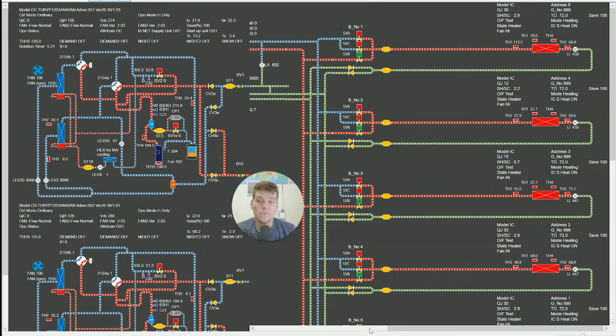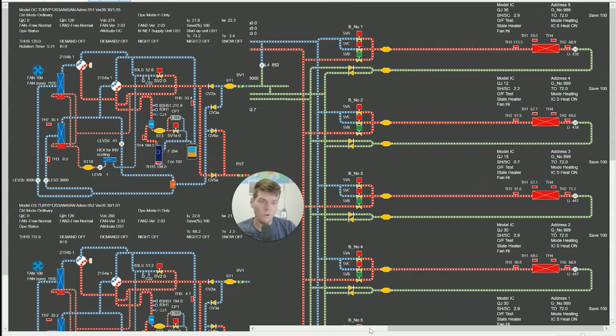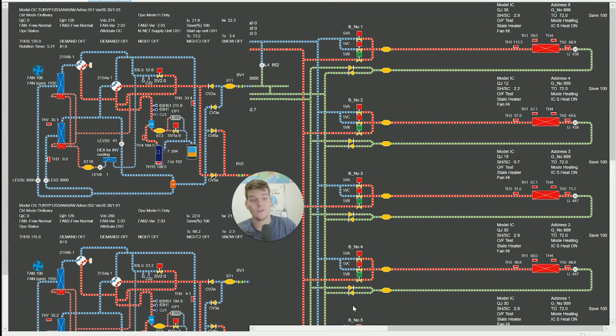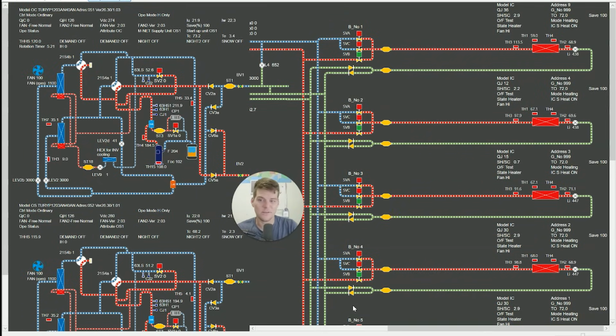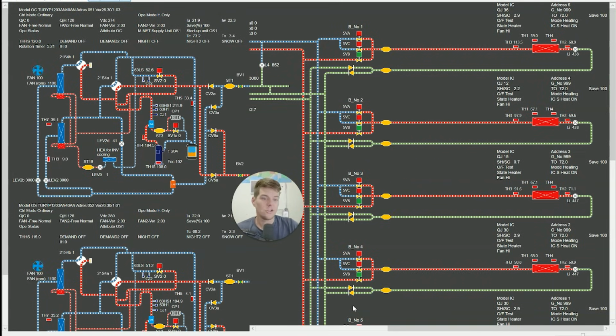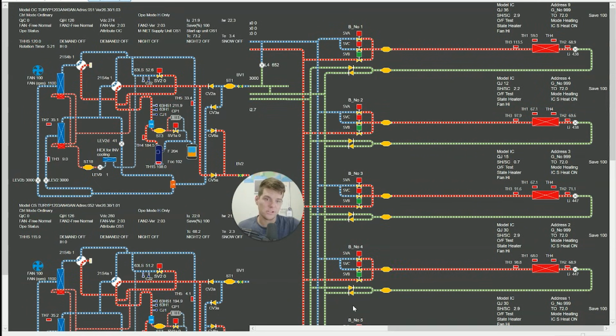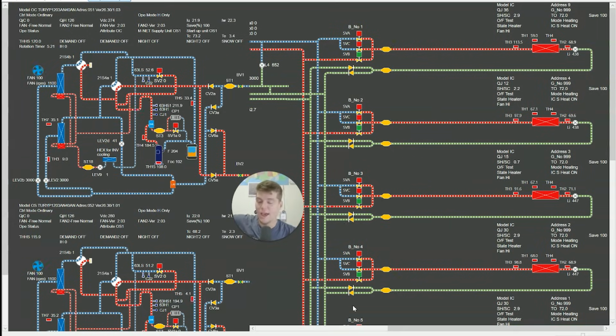But this time of the year, most systems are going to be switching over from cooling to parallel operation or all the way to 100% heating. And in going into 100% heating, there are some things that happen that don't normally happen, right? Especially on this VRF system. We've got a lot of 4-way valves that are shifting. We've got charges that are starting to be shifted in the system and they're going to different directions. Now the indoor units are becoming heat exchangers and the outdoor units are becoming in an evaporative state.